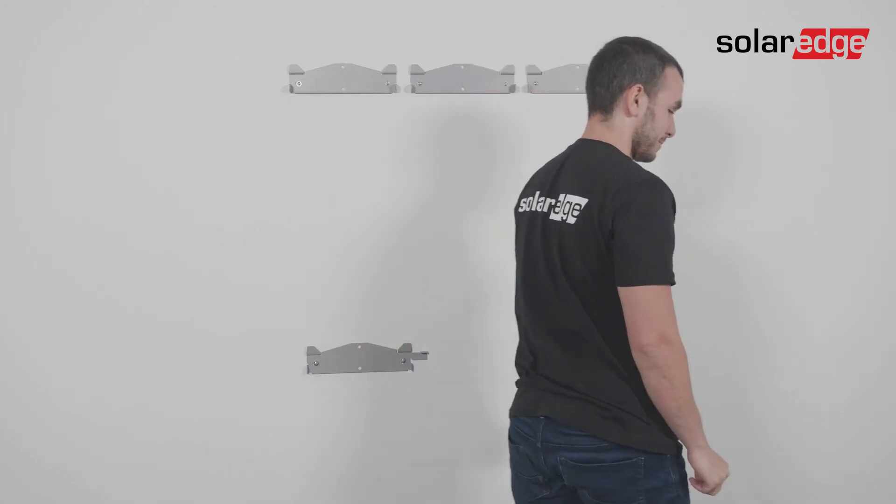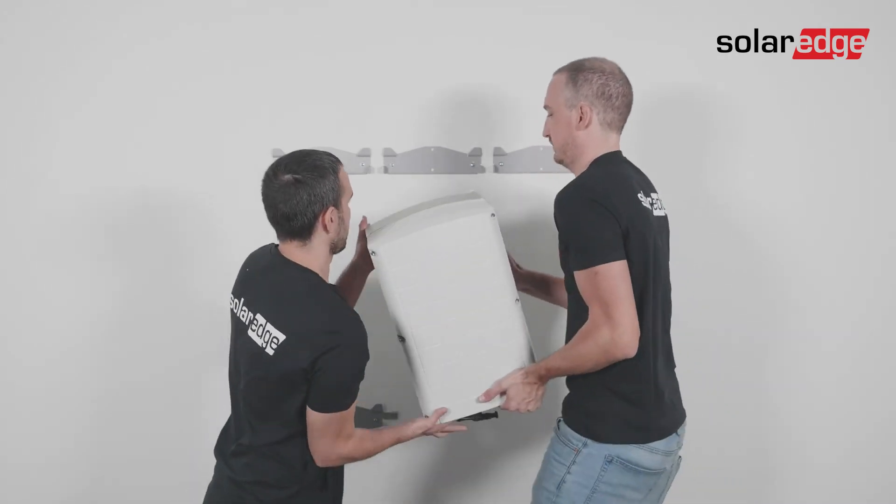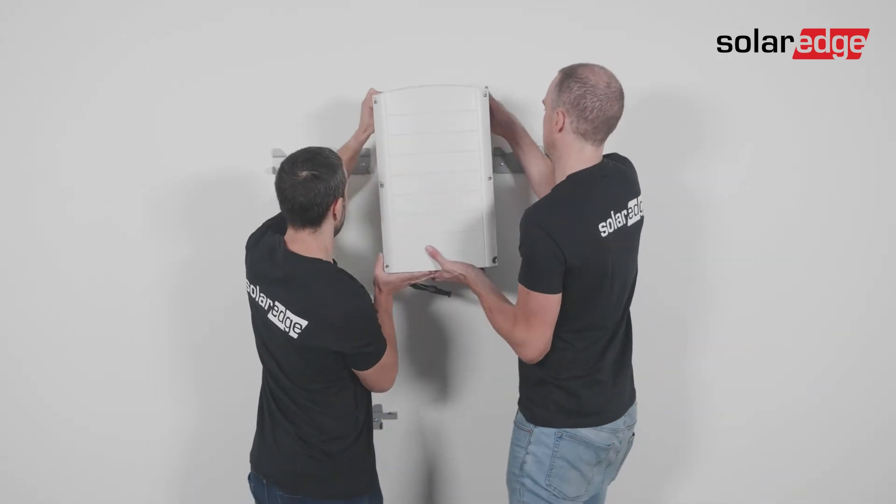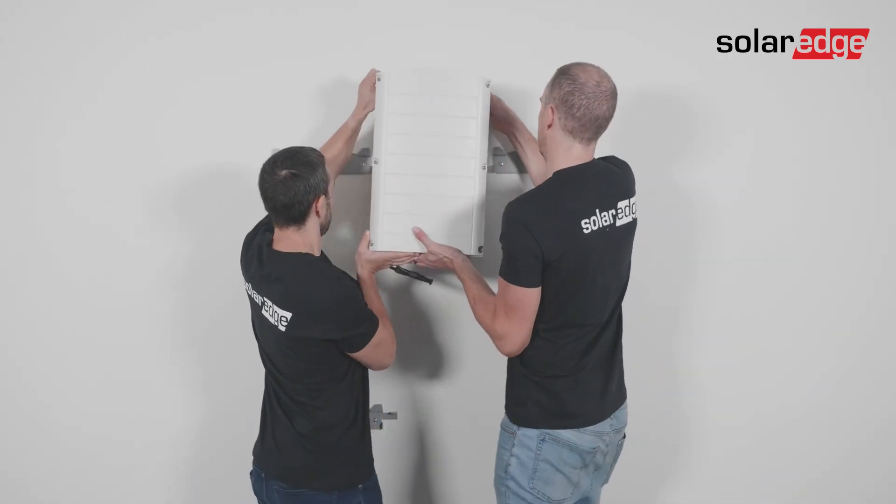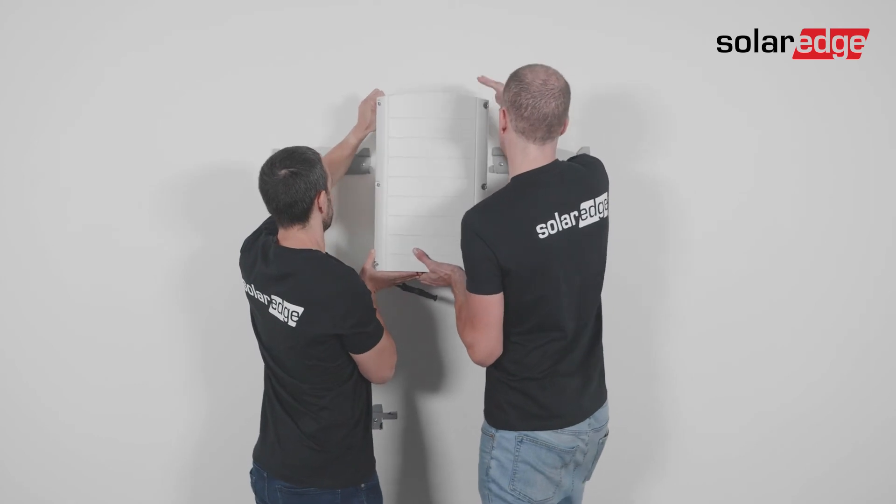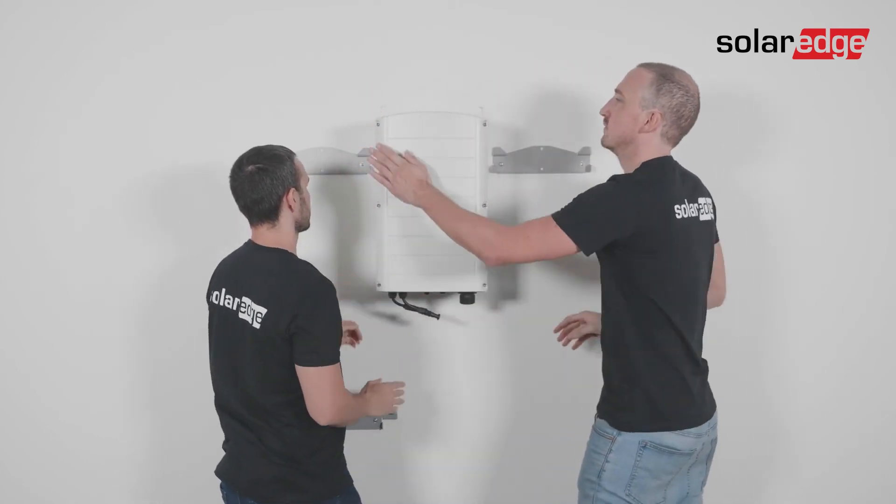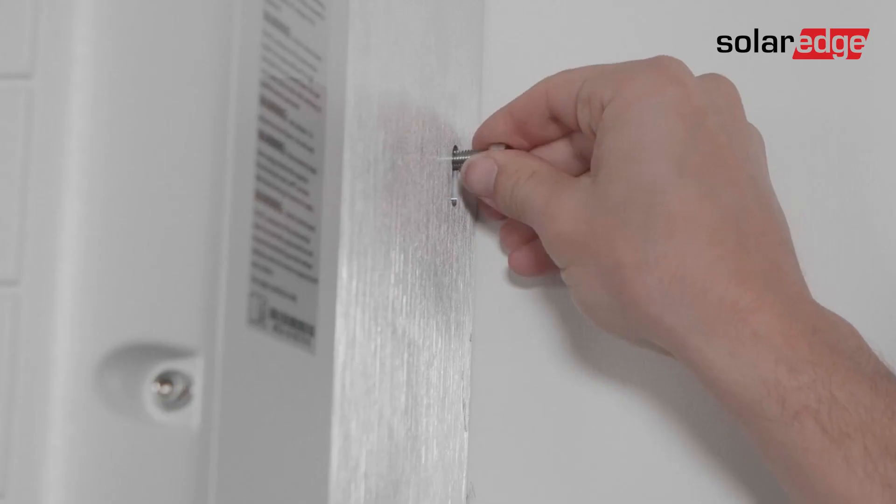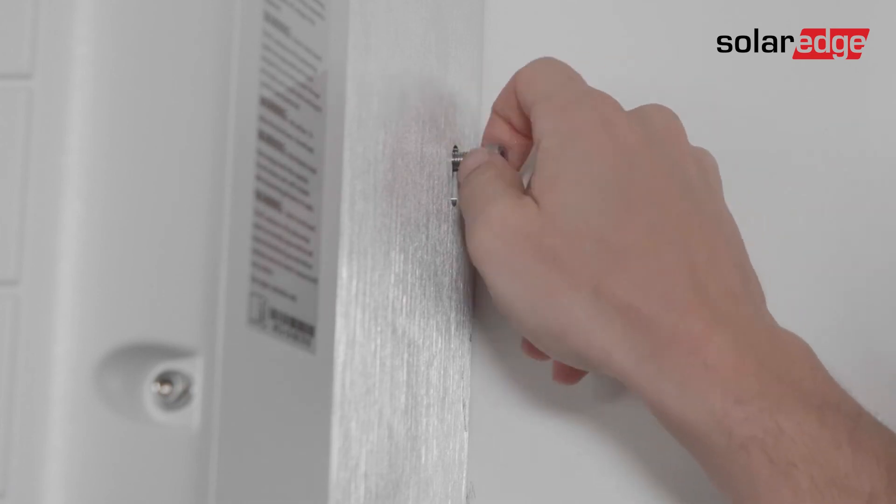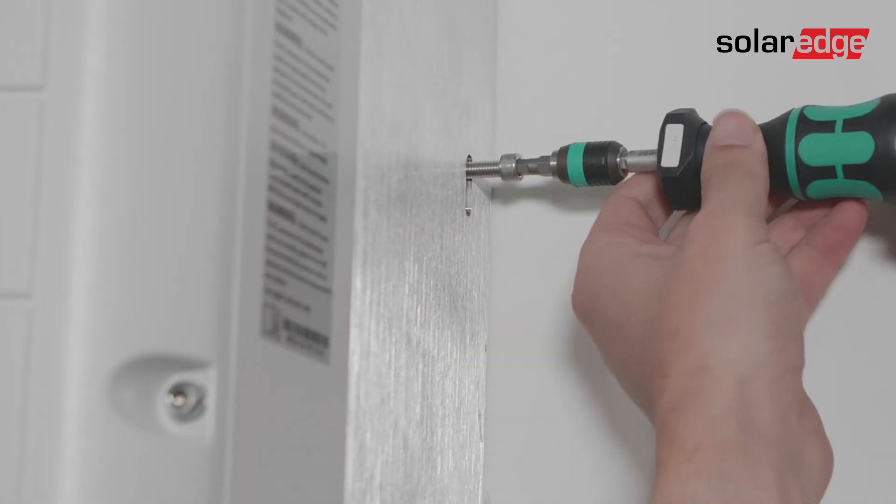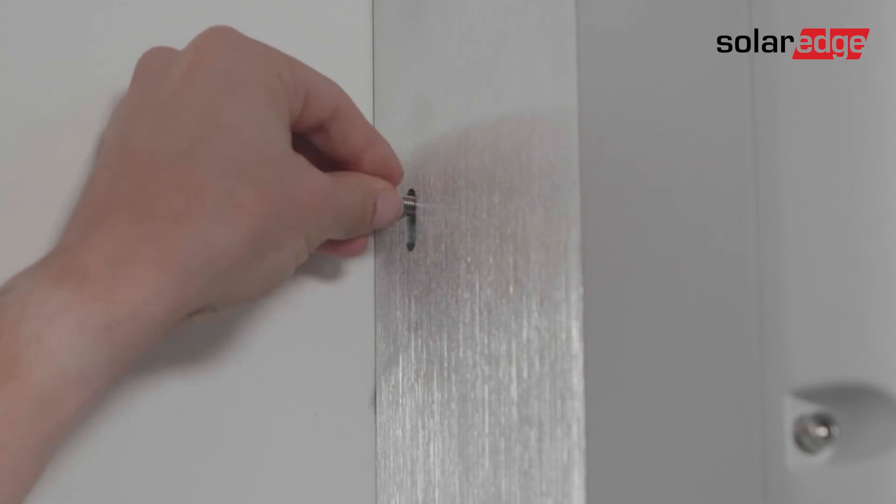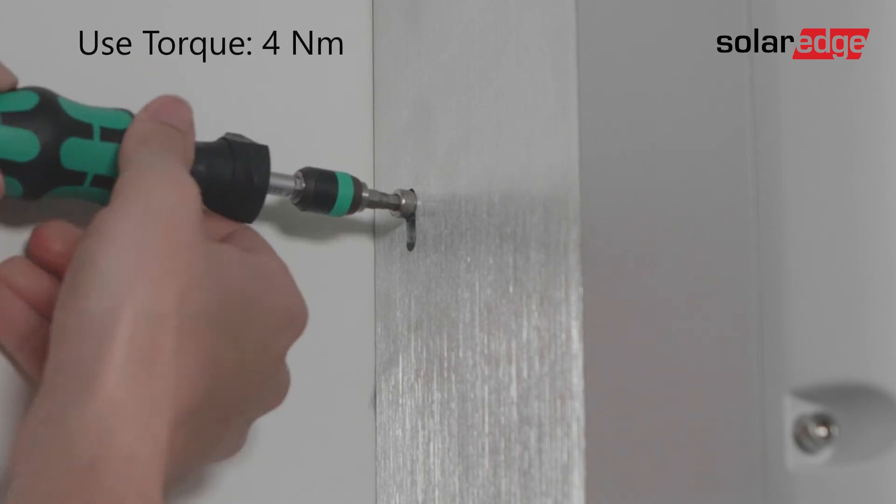Now it's time to mount the Synergy units. Lift the center Synergy unit from its sides. Align the two indentations in the enclosure with the two triangular mounting tabs of the bracket and lower the Synergy unit until it's evenly resting on the bracket. Then insert and fasten the two supplied fixation screws from both sides of the Synergy unit. Use torque of 4Nm.